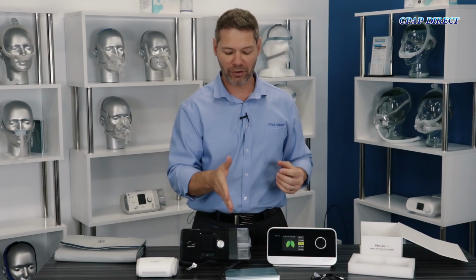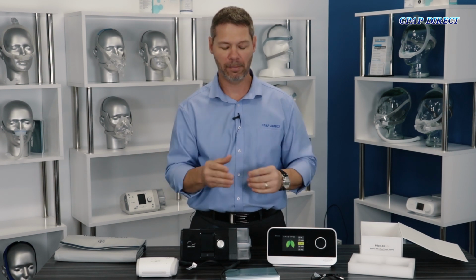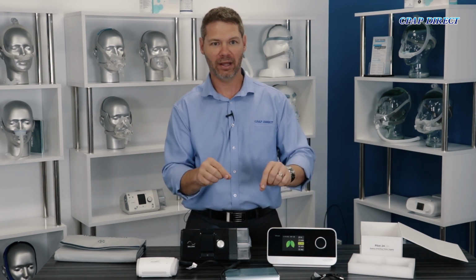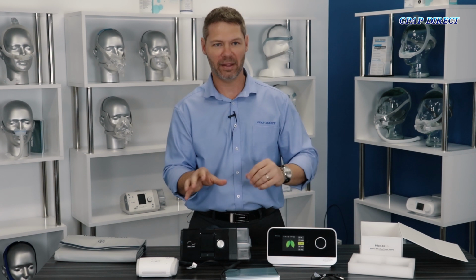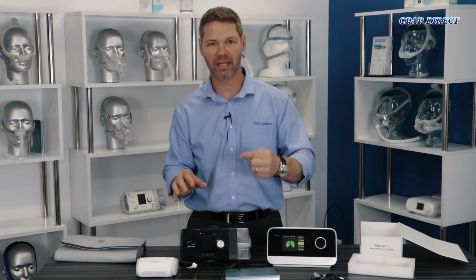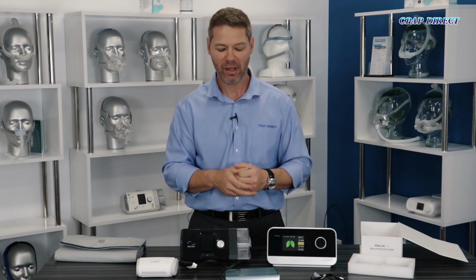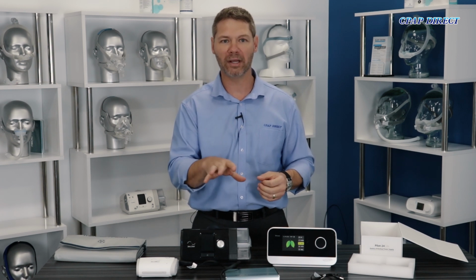Another really important point for the Pilot Lite 24 is that it's also a UPS, an uninterrupted power source battery. That means you can leave any of these devices plugged into the battery at all times, and the battery into the power. So if the power goes out, the battery automatically kicks in, and you won't lose power to your CPAP machine in big storms or disasters that could affect power. It's great from that perspective, meaning you'll always have therapy.